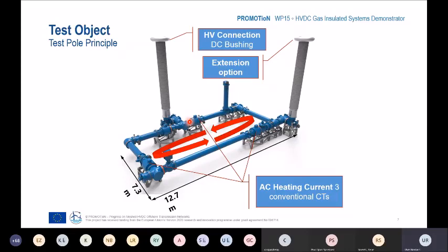So we have under DC conditions a completely different electrical field distribution under no load and under load conditions, depending on the temperature distribution. Therefore, we have also defined different cycles without load and with load to cover all the different field conditions under real situations. Moreover, you can see here the voltage and the RC divider voltage measurement, as well as the current measurement. That is a zero flux sensor in that case.